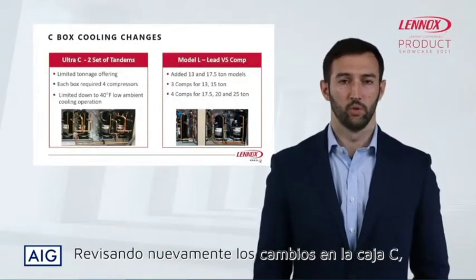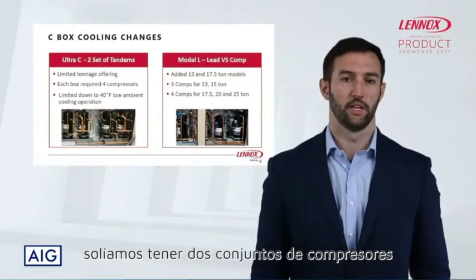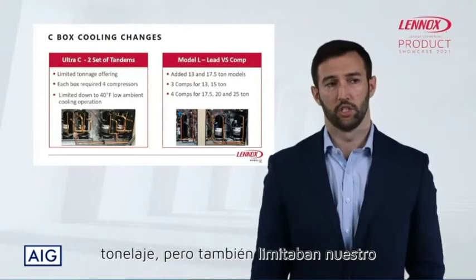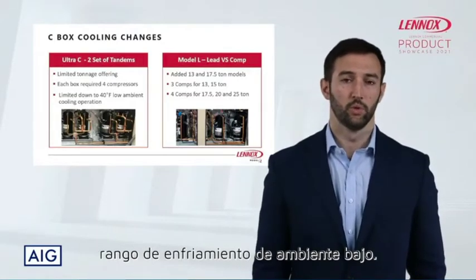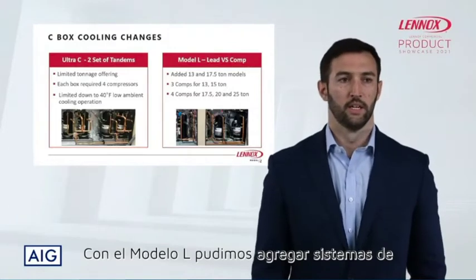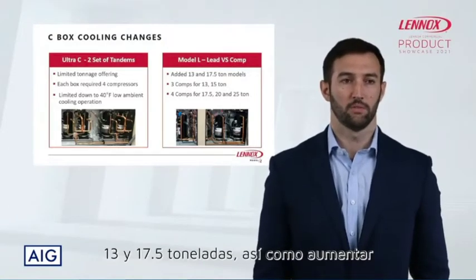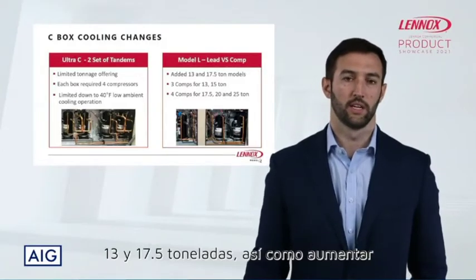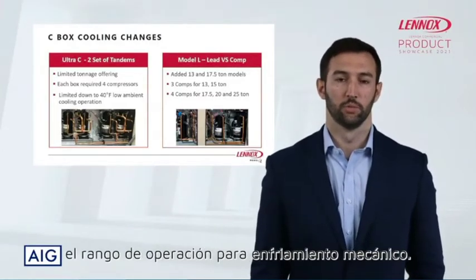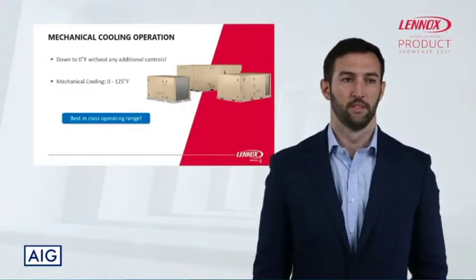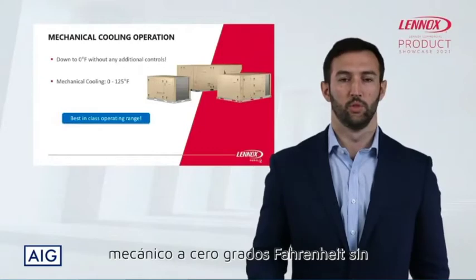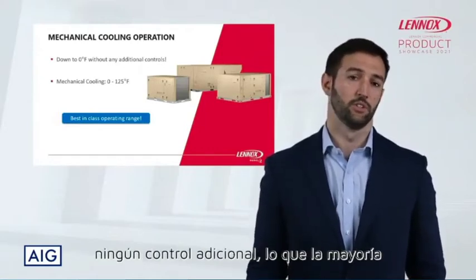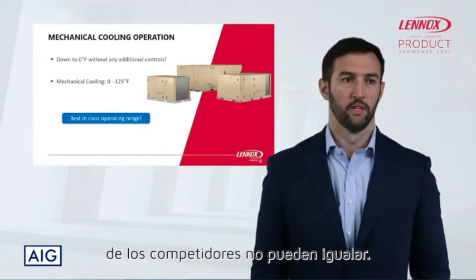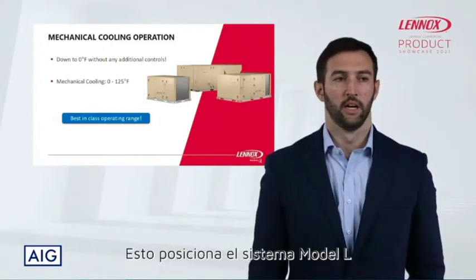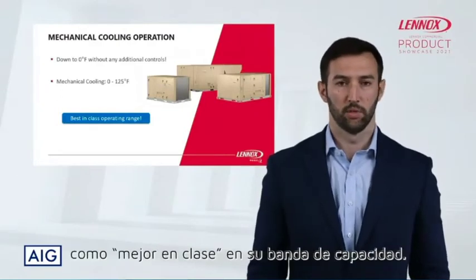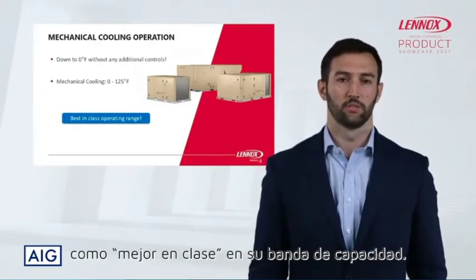Looking again at the C-Box cooling changes, we used to have two sets of tandem compressors that again limited our tonnage offering, but also limited our low ambient cooling range. And so with the introduction of Model L, we were able to add 13 and 17 and a half ton models, as well as increase that mechanical operating range for mechanical cooling. And so, like I said, we were able to operate mechanical cooling down to 0 degrees Fahrenheit without any additional controls, which most competitors are not able to match. And this gives us a best-in-class operating range for cooling with the Model L units.